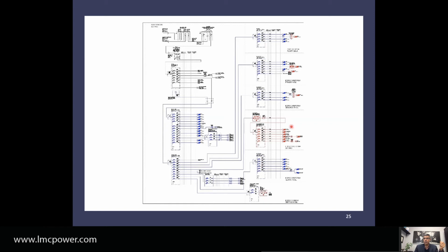On the load side, for some, not all, of their equipment that they felt was critical, they had added another 50 kA protection. So there are rules of thumb, but depending on the installation, you can be creative. At the input, we had category C, we had 2 category Bs, and then we had sub-panels with lower kA ratings, as well as a couple of protected pieces of equipment here. We had some pumps and some controls that they decided to sprinkle a couple of 50 kA surge protectors into. This is a sample of 25 of their buildings; we just received the letter of intent yesterday.